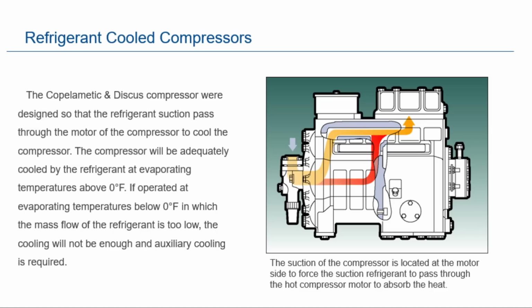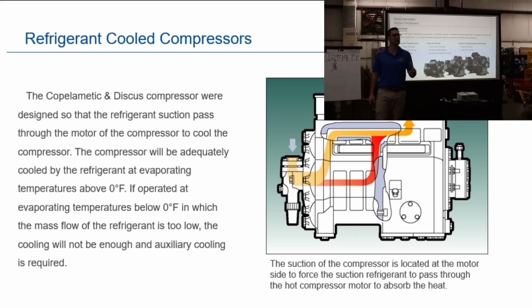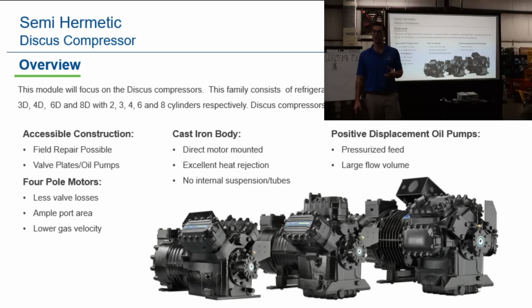Same thing, they're semi-hermetic. You can take them apart, you can look inside. Look inside these compressors. If these compressors fail or if they run into issues, take them apart. We want you to look at them. We want you to find the problem, because if you find the problem, the next one you install, you won't have to replace it after 6 months. That's one of the biggest things that we notice as a manufacturer.